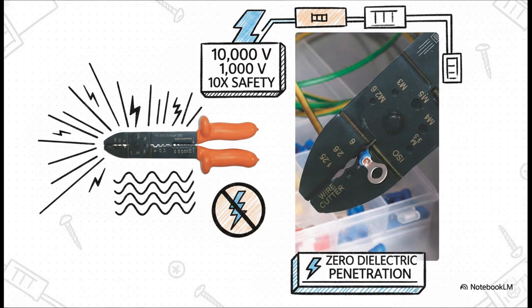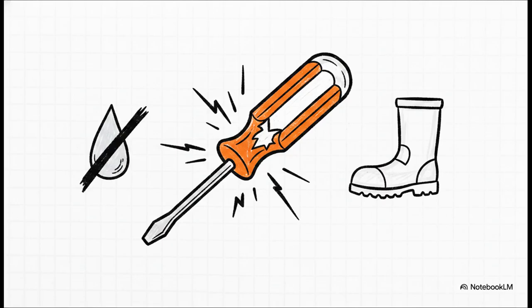It's a critical protective barrier between the operator and potentially lethal electrical currents. To get certified for work on lines up to 1,000 volts, these tools are rigorously tested at 10,000 volts. That's a 10-times safety factor just to ensure absolutely zero dielectric penetration. Pretty wild, right? The international standard governing all of this is IEC 60900.